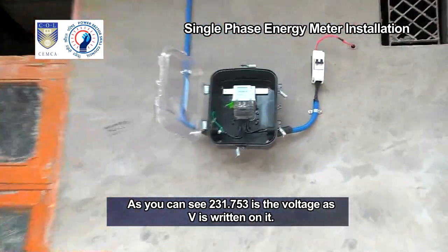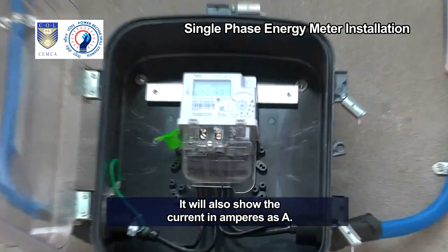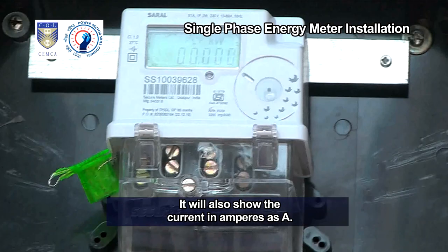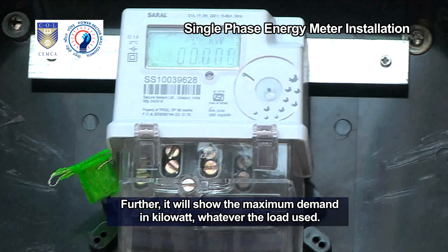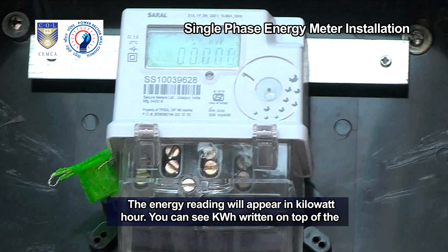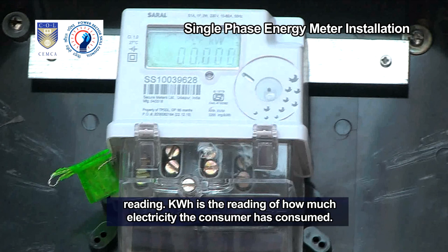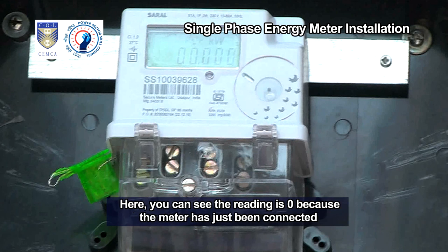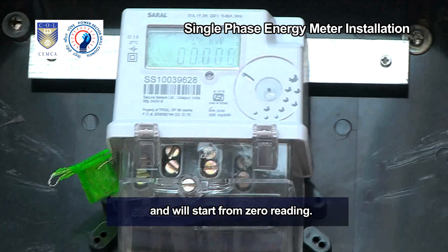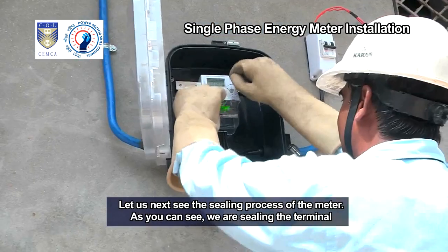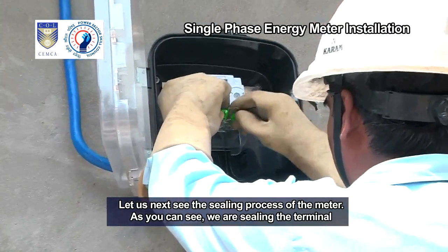231.753 is the voltage as V is written on it. It will also show the current in amperes as A. Further, it will show the maximum demand in kilowatt, whatever the load used. The energy reading will appear in kilowatt hour. You can see kWh written on top of the reading. kWh is the reading of how much electricity the consumer has consumed. Here, you can see the reading is 0 because the meter has just been connected and will start from 0 reading. Let us next see the sealing process of the meter.